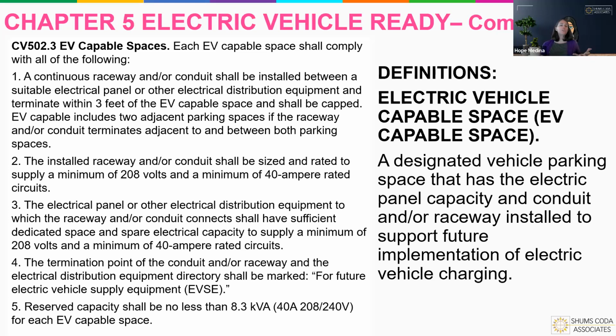You do have to make sure there's at least a 40 amp rated circuit. The electrical panel has to have that dedicated space, and you have to have that termination point for the conduit and raceway for future use of the equipment. I'm not sure how that will be labeled, but I'm sure we'll figure out a way to make it readily available.